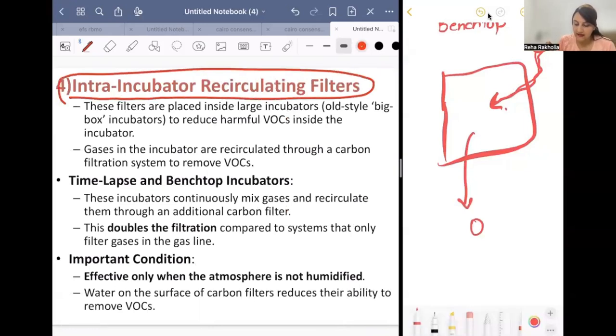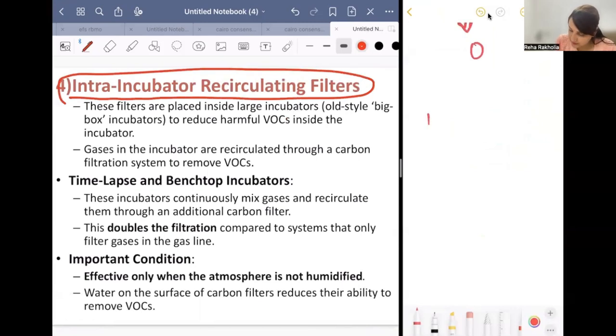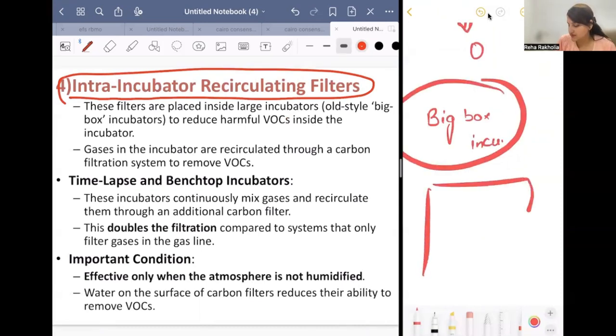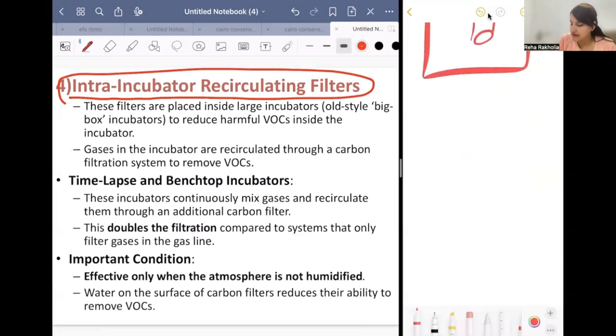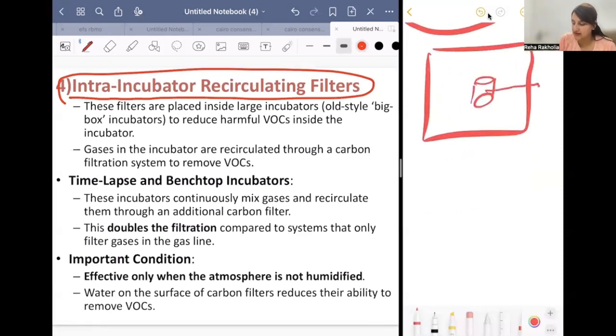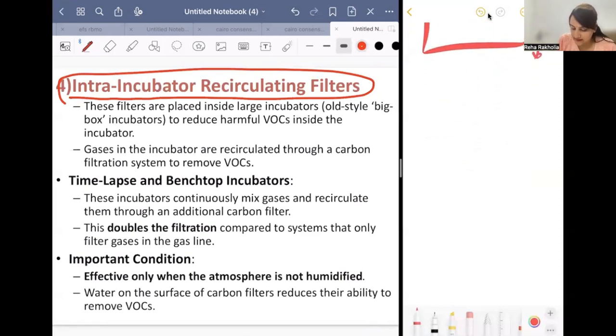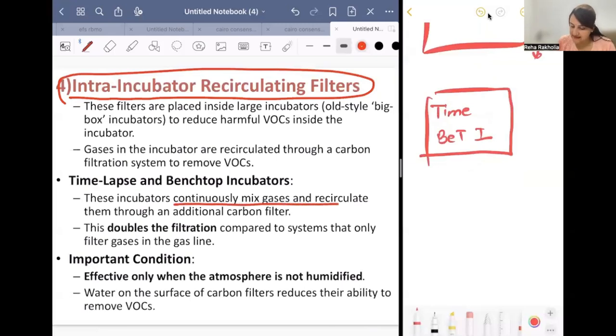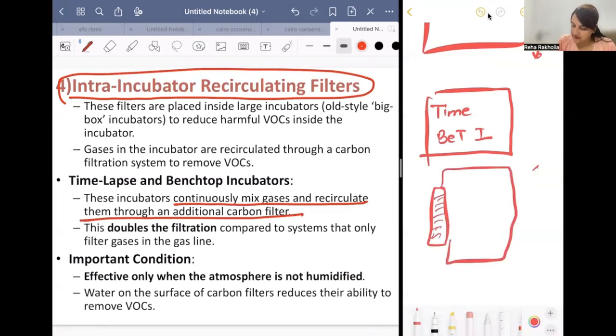Intra-incubator recirculating filters. Now inside the incubator we also have some filters. In the big box incubator, gas is recirculated through some carbon filters inside the incubator. And the time-lapse and benchtop incubators continuously mix gases and recirculate them through an additional carbon filter. So there will be an inline filter, and inside there will be a carbon filter. This is double the filtration compared to a system that only filters gases in the gas line. It will filter from here also.